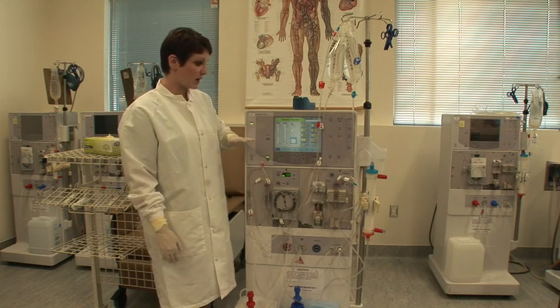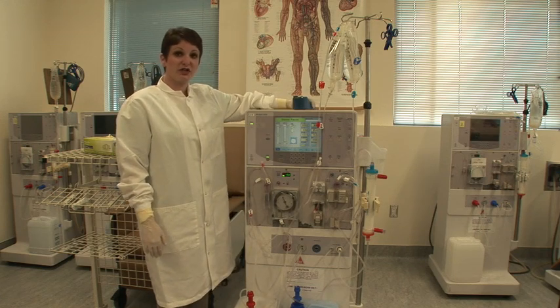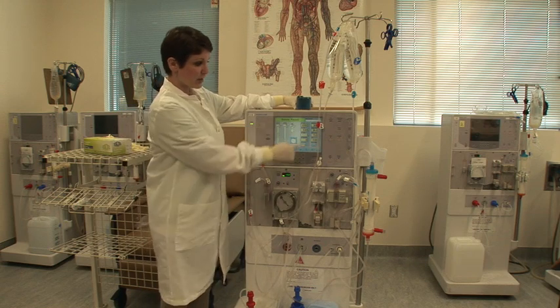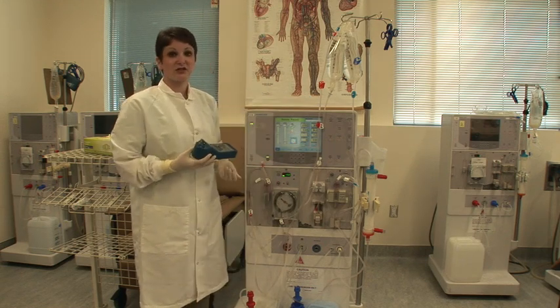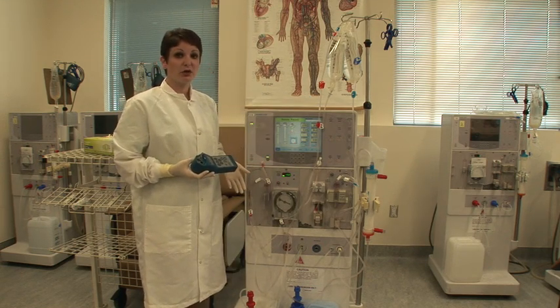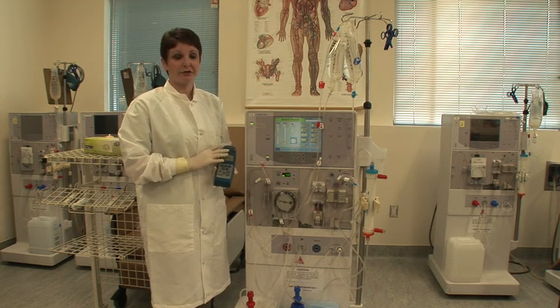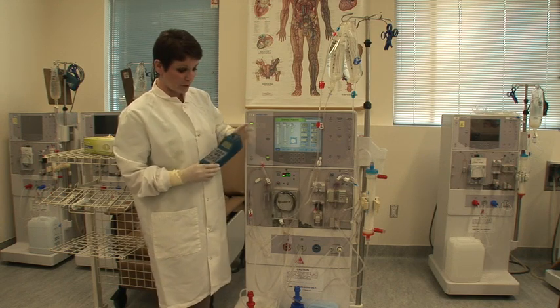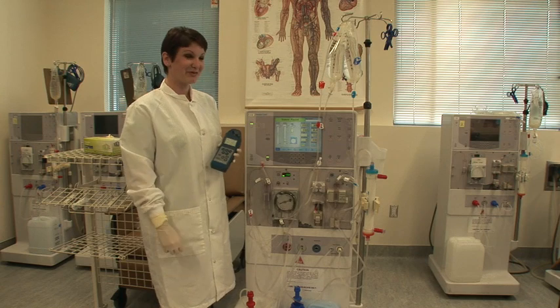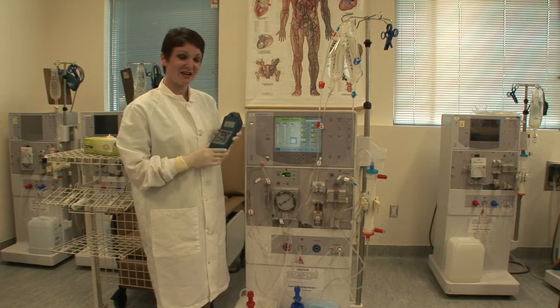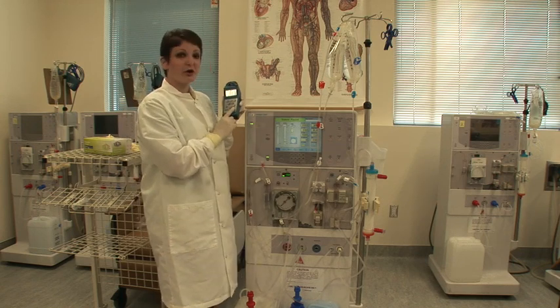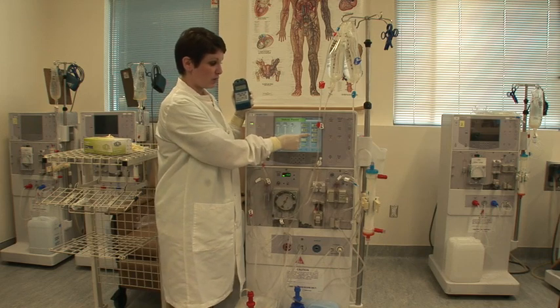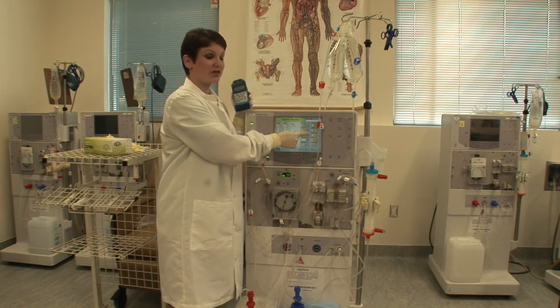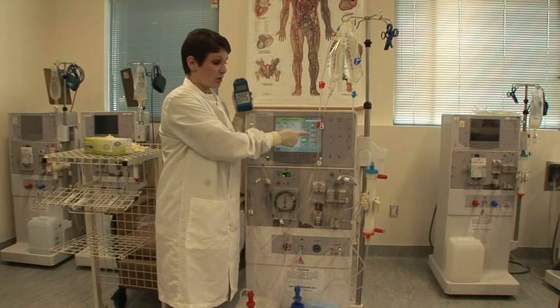It's not as complicated. And the first one we're going to do is check our conductivity and make sure that it matches up with our machine. For this, there are lots of different machines that we can use. In class, we use the Myron L. When you're checking your conductivity, you want to make sure that the reading on your Myron L is within 0.2 of your reading on your machine.